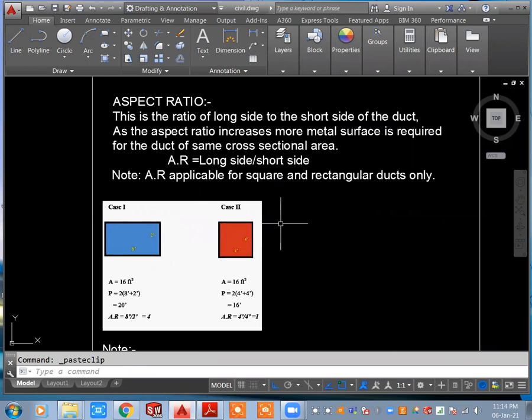Now I am explaining about aspect ratio. What is aspect ratio? It is the long side divided by the short side of the duct — that is the correct meaning. By using this aspect ratio, we can control our cost, balance our fabrication cost, and balance our entire HVAC service cost. This aspect ratio is only applicable for rectangular and square ducts, not for circular or oval ducts.